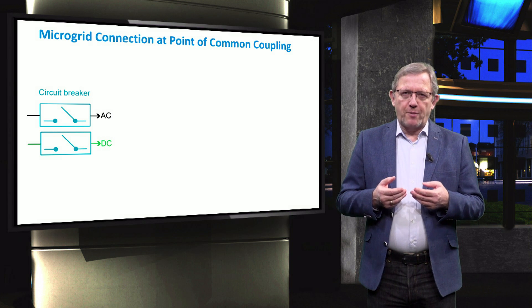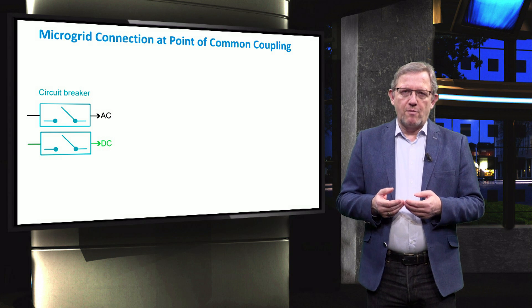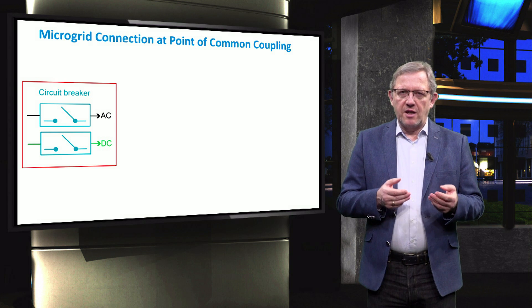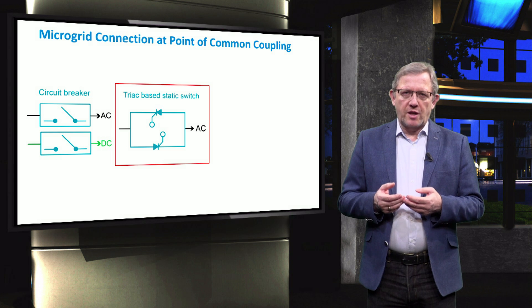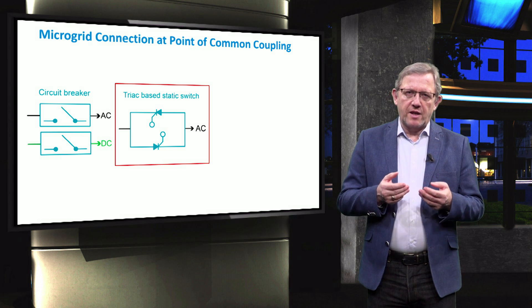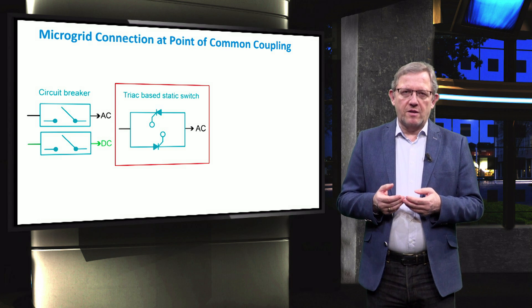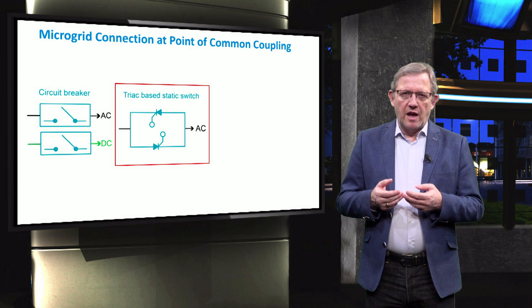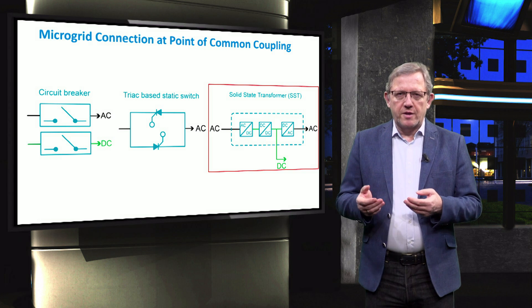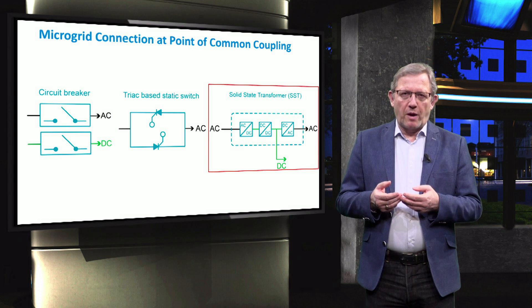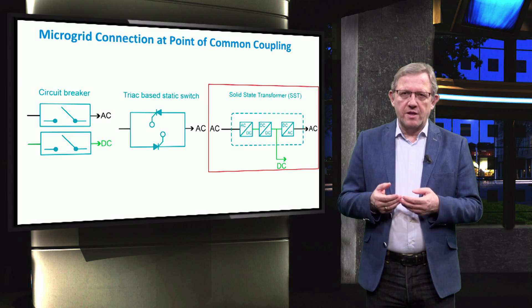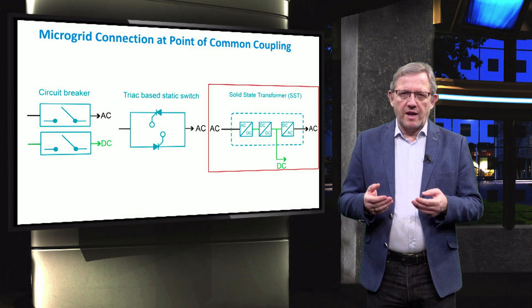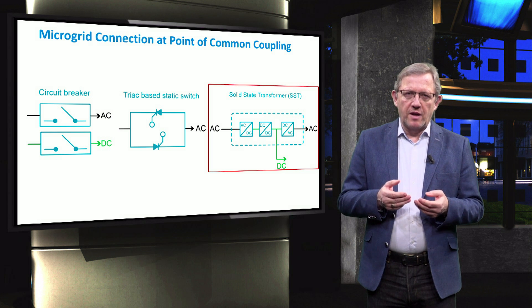The microgrid can be connected to the upstream network through various electrical components. The most commonly used component is a circuit breaker, which could be either AC or DC. The second is a static switch, which is a semiconductor-based driven switch controlling the microgrid for either grid-connected mode or islanded mode. The typical power semiconductor used for the implementation of a static switch is a triac, like the one shown in the figure, but many other circuits have been proposed in the literature. The triac is the preferred option because it supports large overcurrents, even kiloamps during some grid cycles.